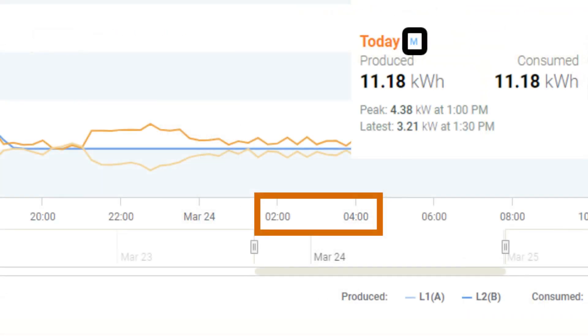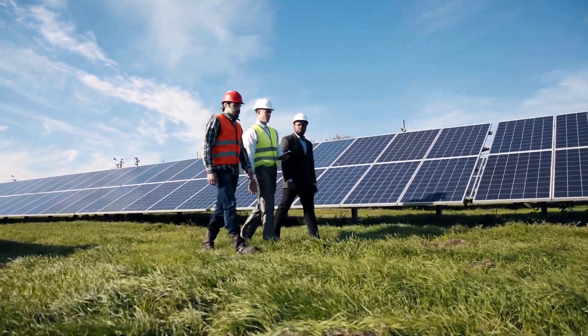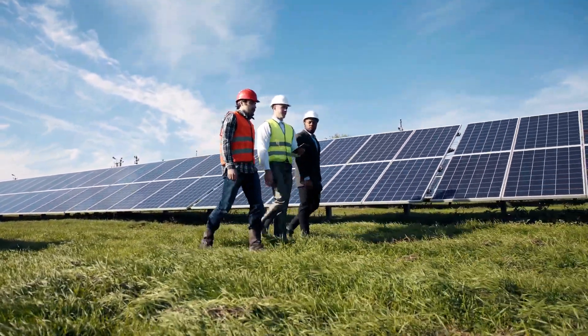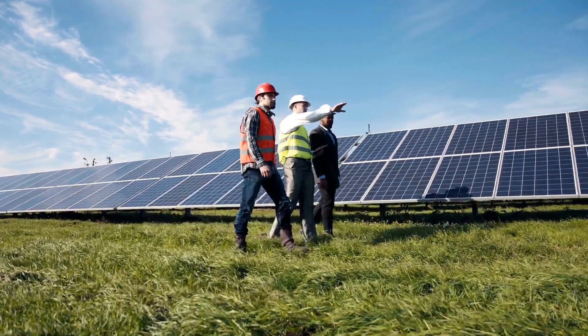If the consumption readings include overnight reporting of the consumption, you have proven the issue to be related to the physical installation of the CTs. In this image you can see consumption is reporting overnight in the graph view of the installer portal.